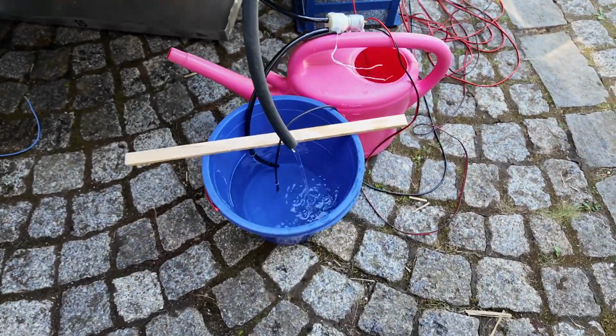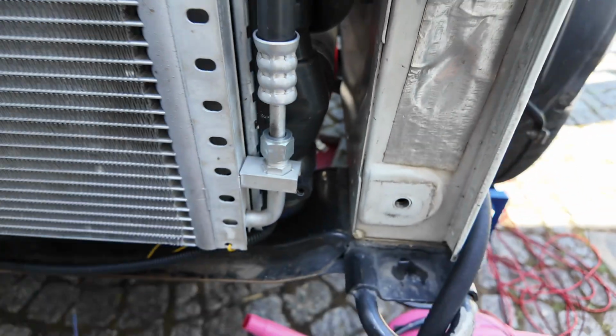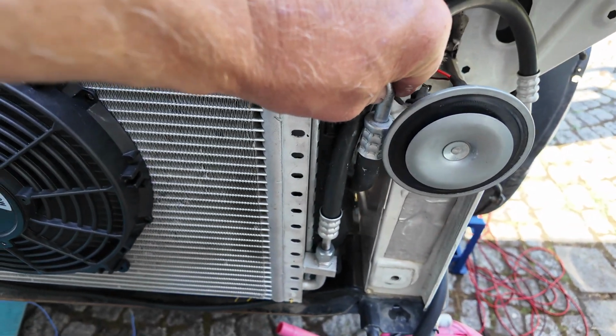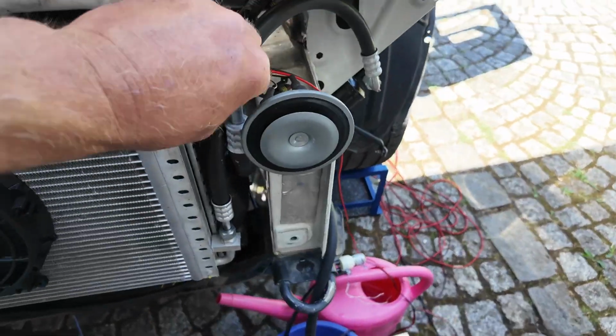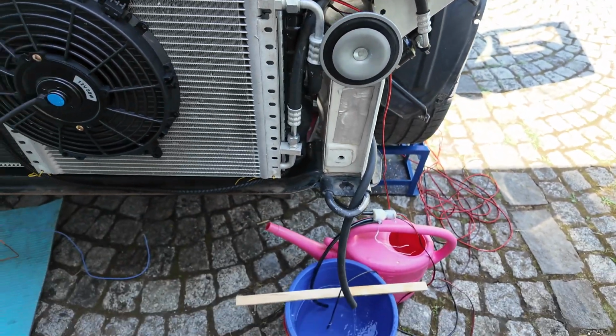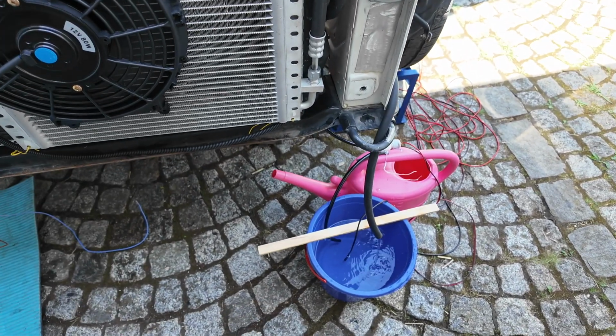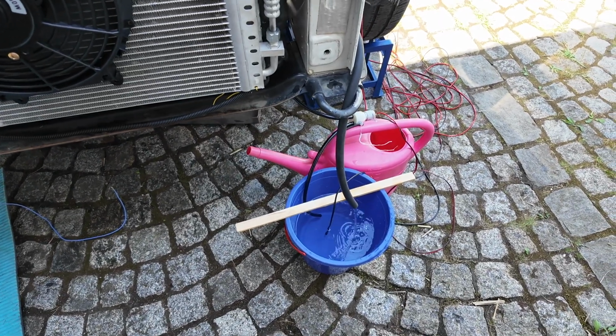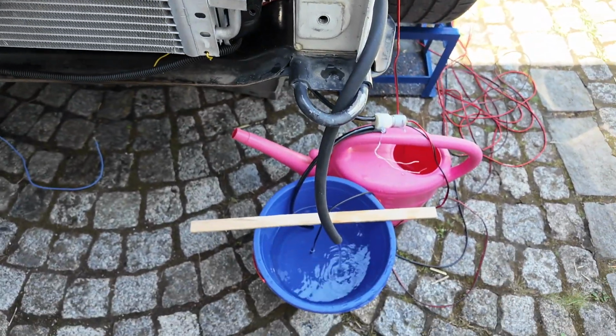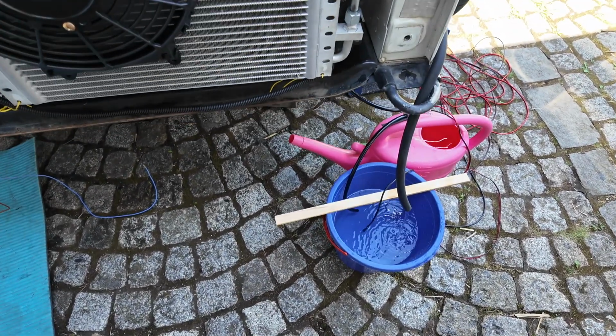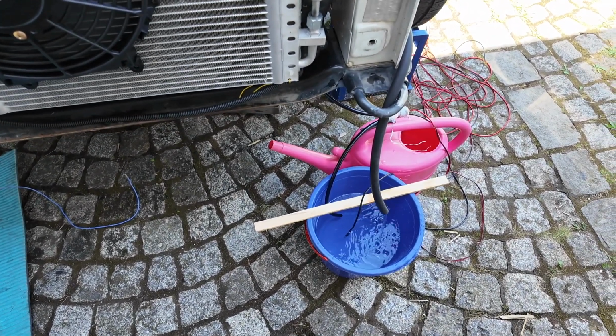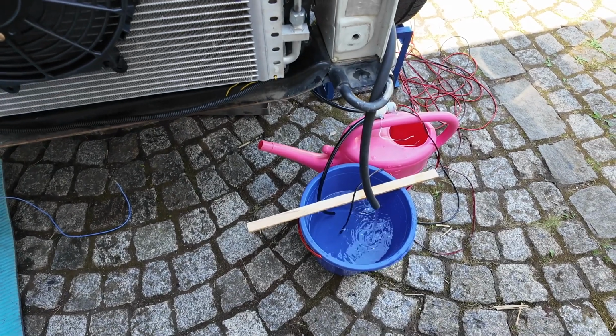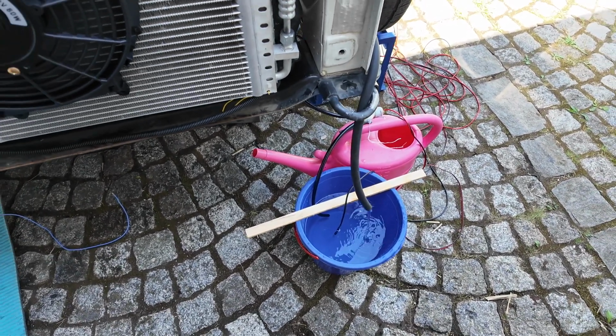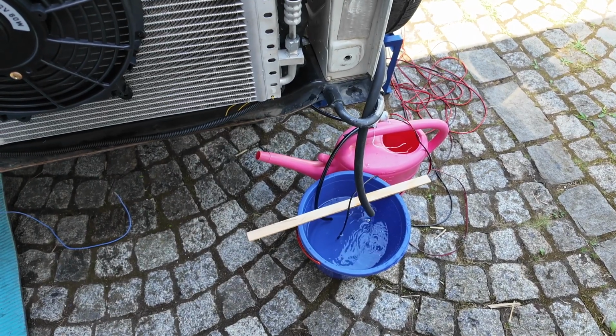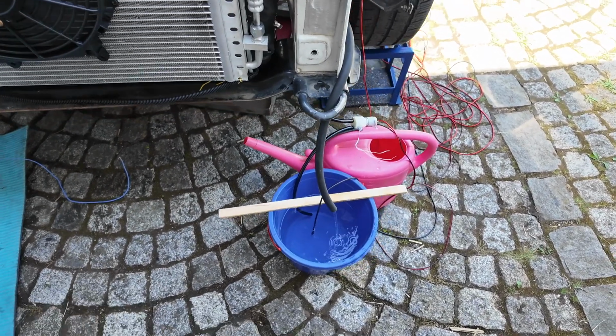I just realized the plate heat exchanger is not pulling all the heat energy out of the refrigerant, because this is still way hotter than the water coming out of here, which means we cannot use this method to determine the performance. Too bad, but at least we generate hot water for free while running the air conditioner. And this is a big win. And yeah, we can still calculate how much energy goes in there in kilowatts, but I guess it's way lower than what it could be if we had a properly sized heat exchanger.